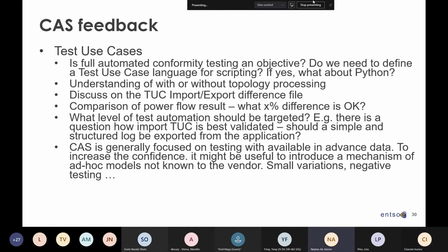Yeah, okay, but anyway, also when we import something and we do load flow, and we have problems in the load flow, then we see it all in the messages. Also, when a line length is 0, then we see in the tool that load flow is not running because of line length 0 or another problem. Also, if the load flow runs, and if the results are correct, then the import is correct.